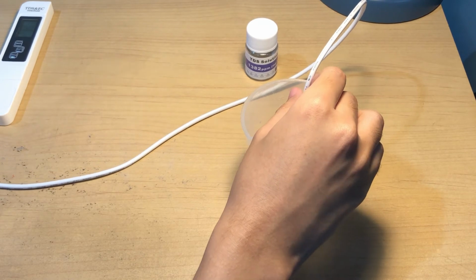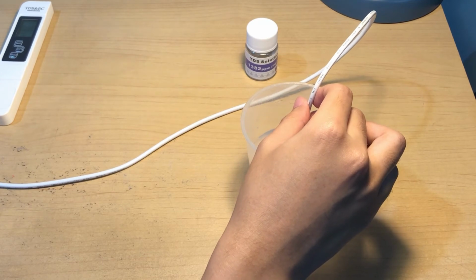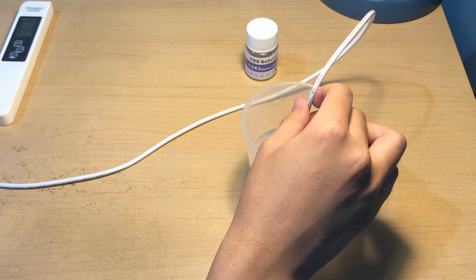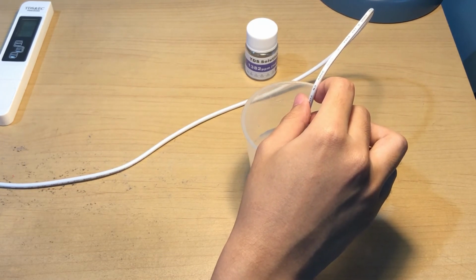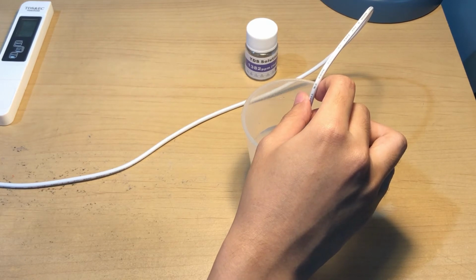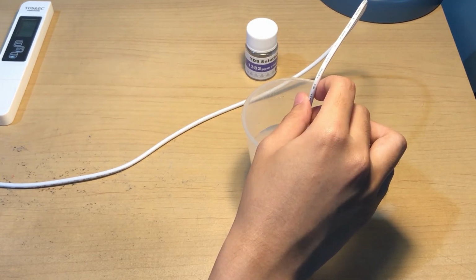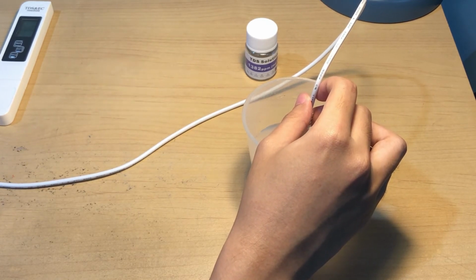In the meantime, I'm going to open the serial monitor so that we can enter the calibration mode. To enter the calibration mode, just type ENTER and then write the amount of ppm read by the TDS meter used previously. Just write CAL:590. And now this TDS sensor has already detected 590 ppm in the serial monitor. And to exit, we need to type exit so that it can save the value. And now the calibration process is successful.